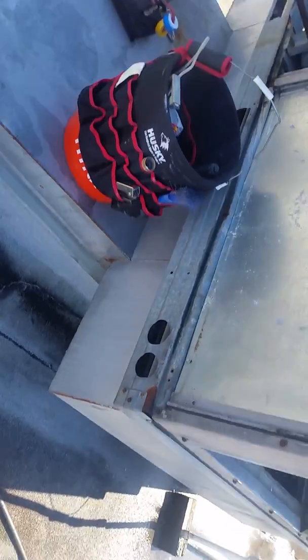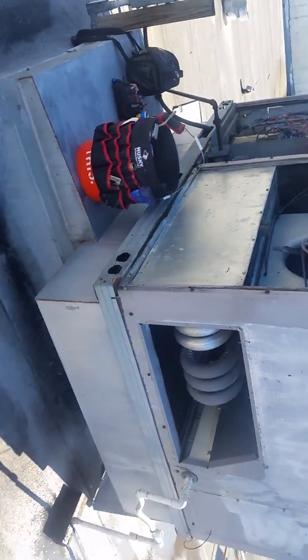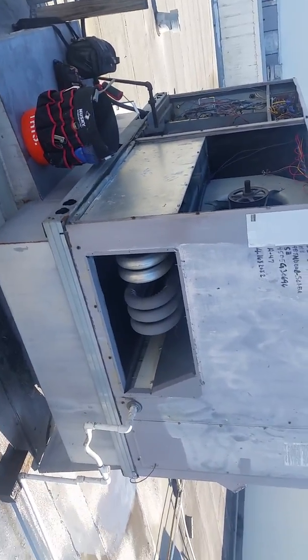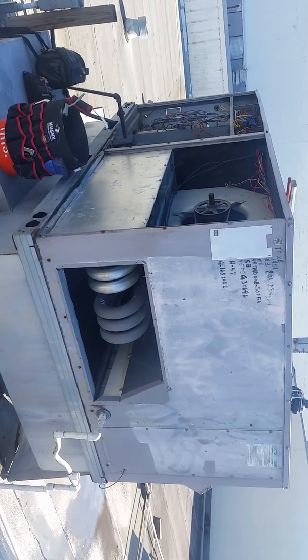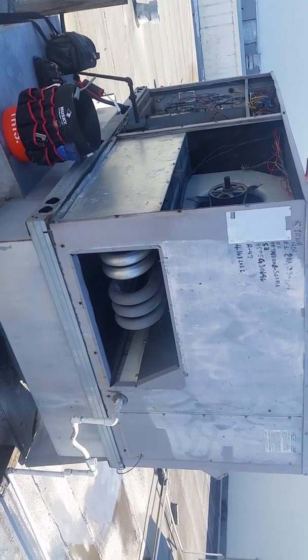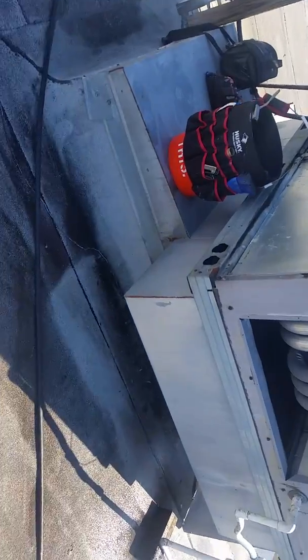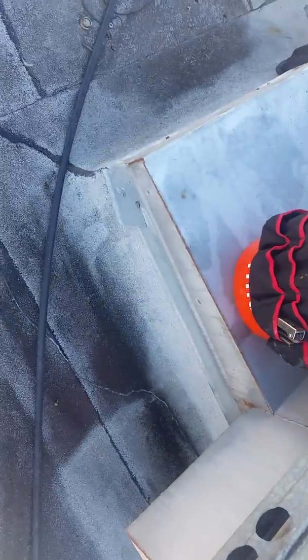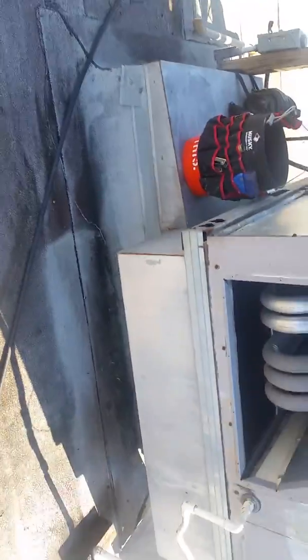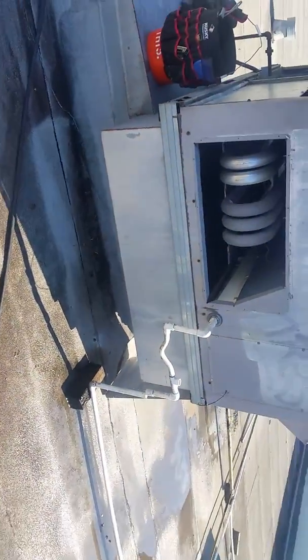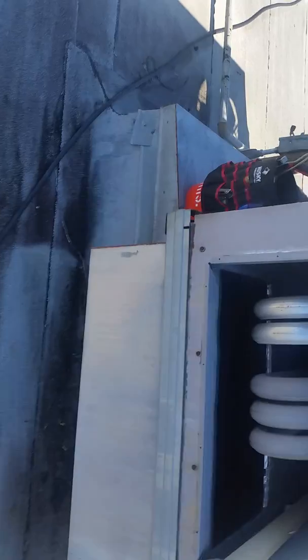Just as a reminder, if you end up replacing this unit with something outside of a Carrier or outside of this model number, if you're going to need a curb adapter, you're not going to be able to go with the curb adapter once again, because you already have a curb adapter. So what has to be done is that we're going to have to curb the unit from the bottom.